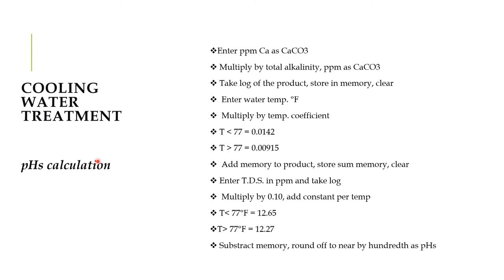For pH saturation (pHs) calculation: enter calcium hardness in ppm as CaCO3, multiply by total alkalinity in ppm as CaCO3, and take the log of the product. Enter water temperature in degrees Fahrenheit — multiply by 0.0142 if less than 77°F, or 0.009 if greater than 77°F. Add both values. Enter TDS in ppm and take its log. For temperature correction, multiply by 12.65 if less than 77°F, or 12.27 if greater than 77°F. Round up the result to get the pHs.